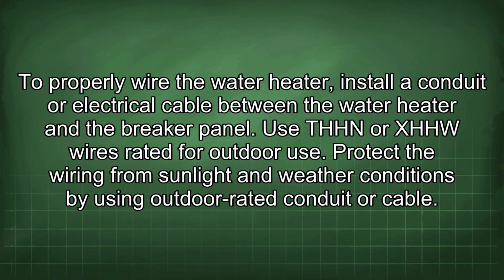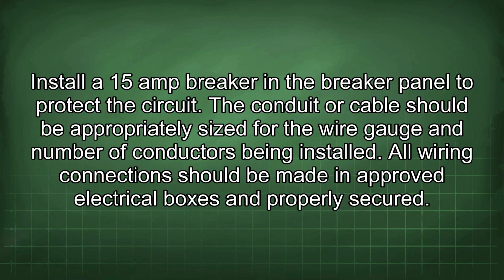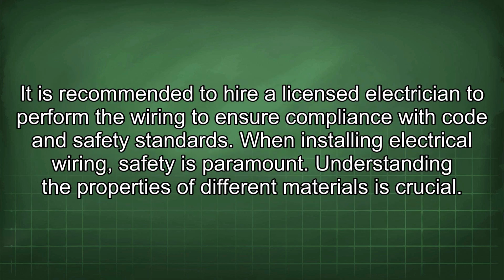Use THHN or XHHW wires rated for outdoor use. Protect the wiring from sunlight and weather conditions by using outdoor rated conduit or cable. Install a 15-amp breaker in the breaker panel to protect the circuit. The conduit or cable should be appropriately sized for the wire gauge and number of conductors being installed. All wiring connections should be made in approved electrical boxes and properly secured. It is recommended to hire a licensed electrician to perform the wiring to ensure compliance with code and safety standards.